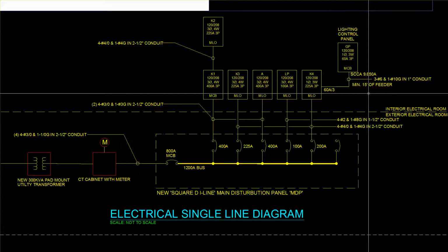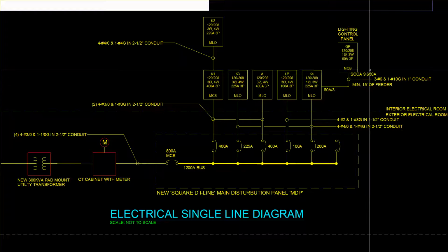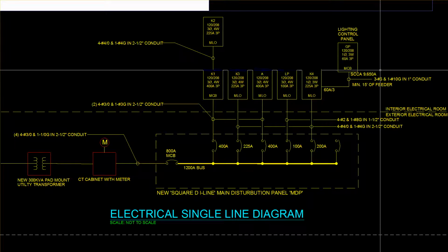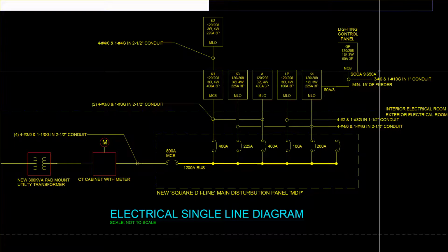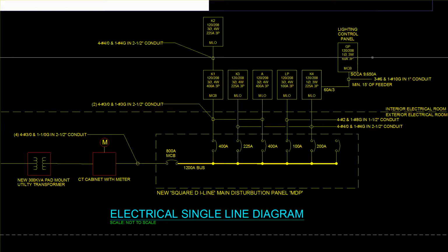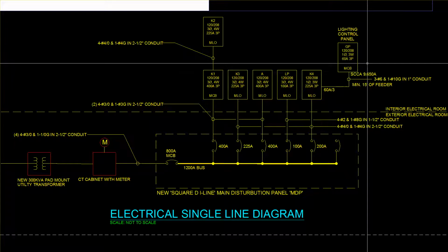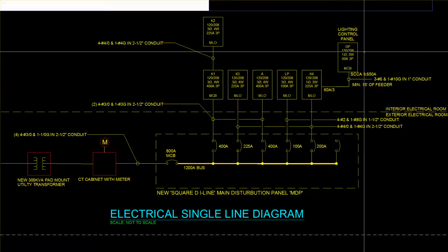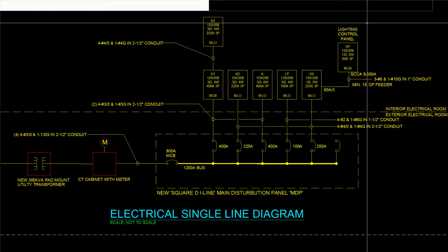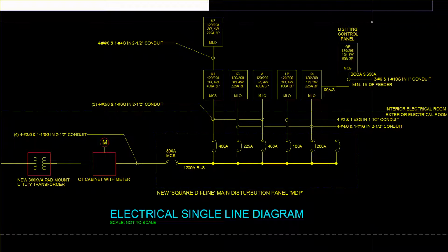Also, one of the things you'll see here is this SCCA, short circuit current available, of 9,650 amps. Now, in some one-lines, that's what you'll see, because for most building departments, and certainly for your engineering study, you have to put that information. You have to know what these breakers and these panels are designed to withstand. Circuit breakers are rated at different levels in the tens of thousands, so 10 to 22 to 35 to 45 to 65, 100, etc. Different short circuit current ratings, or bracings, as some people know them.